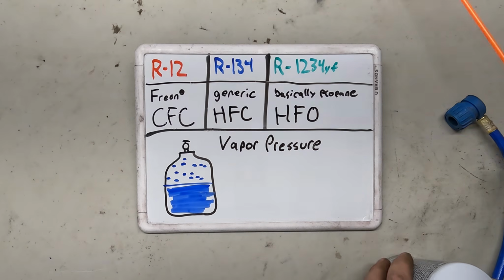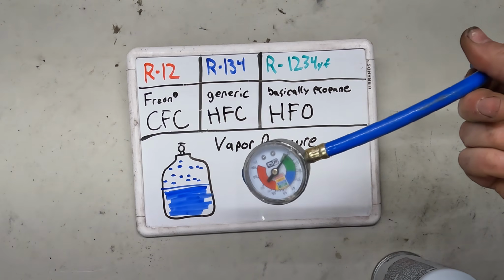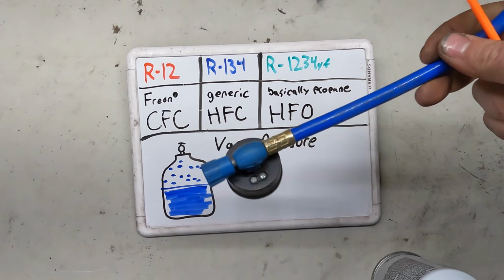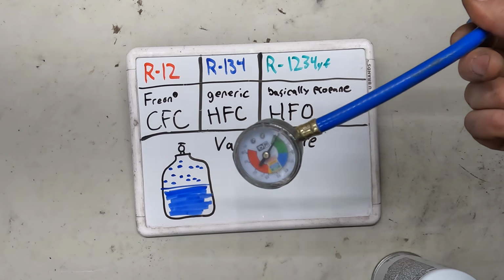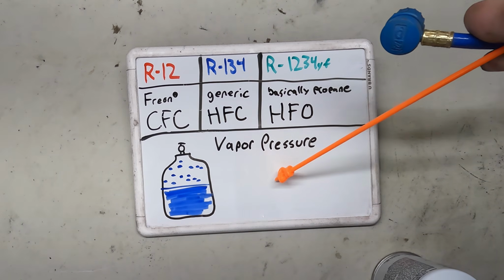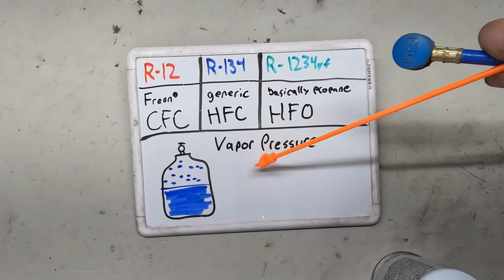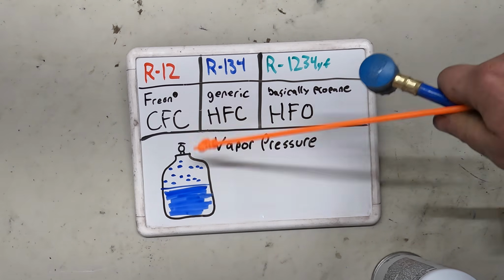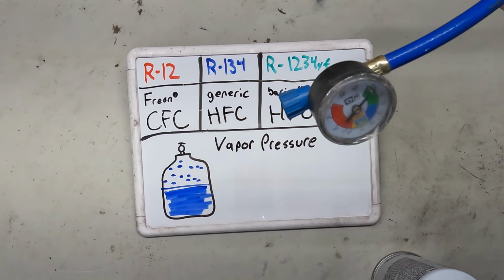This is why, to know how much propane is in a cylinder, you have to weigh it. And also why, if you just look at the pressure of the low side of your system, you have no way of knowing how much refrigerant is physically in there. The only way to get the right amount is to completely evacuate it and recharge it. You also may have a sight glass, but given how complex the system is, that doesn't do you much good.